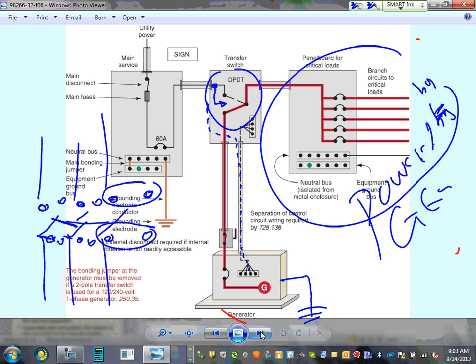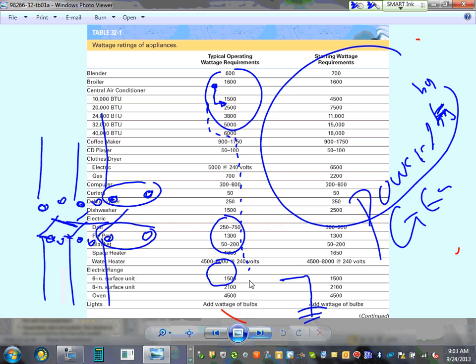I want to bring to your attention, guys, this disconnect here. If you don't have access to this disconnect, then you have to have a disconnect for the generator. Typically, the generators have an access. You have a door, and there's a disconnect. You can disconnect the generator. So that's top of the line, what you're going to do.